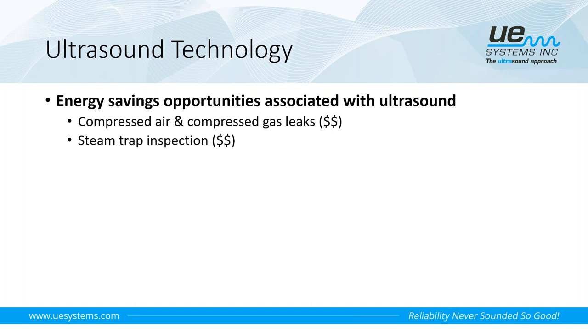So not only can we identify compressed air leaks or failed or faulty steam traps, we can also quantify them, and we can actually put a dollar amount to how much they're costing you. When people are first getting into the technology, the energy savings applications are typically where they start, because it's easy to do, and it's an easy way to justify the cost of investing in ultrasound.